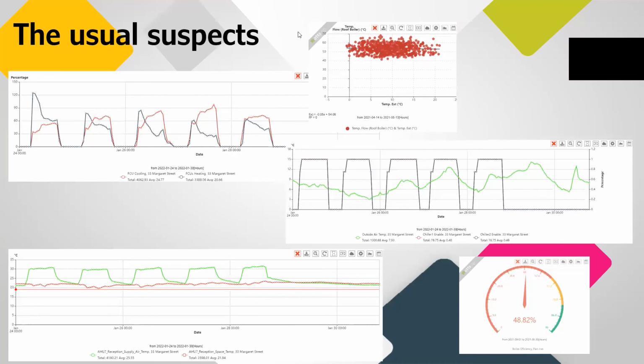Things that have been left on when they weren't required. Valves that got stuck in position, so they were faulty and therefore providing heat where it wasn't needed. But the BMS didn't pick up on that, because the signal was to close the valve, and the valve reported as being closed, but physically was stuck in an open position. Loss of efficiency, equipment that was running outside operational hours, but also programming issues such as the non-following of weather compensation settings in your BMS.